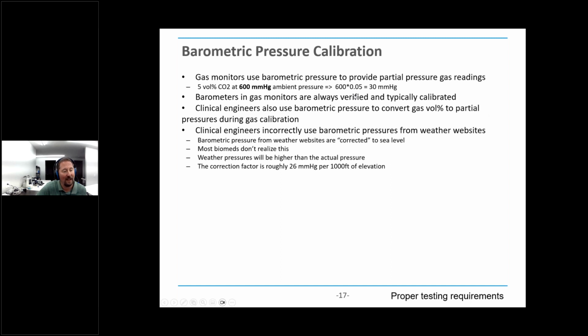The problem we found, as we were talking to people, is that a lot of people incorrectly use weather websites to get their barometric pressure. What they don't understand is that these are all corrected to sea level. So if you're at any elevation at all, it's going to be a higher reading than the actual reading. We had a customer call us one day. They had just gotten their SmartTank and they called us and said, this thing's giving me wrong readings. After a while, we realized that he'd been using these readings and had calibrated incorrectly and was off by quite a bit because of that. But with the SmartTank, they were able to calibrate and get it correct.